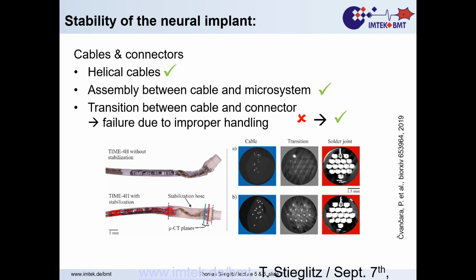Pulling out is one thing. Imagine you would try to get that into the power socket just by pushing somewhere, right? That's even worse. And that's what they did in the rehab center. They did not take the connectors, but really pulled and pushed on the cable exactly here. And that means you have a lot of forces there. And we did not anticipate that because it was so easy. After knowing that, we just put a lot of silicone rubber and more tubing around, and it was problem fixed. Yeah, and we made up our mind about so many things, but not about those 2 centimeters there.